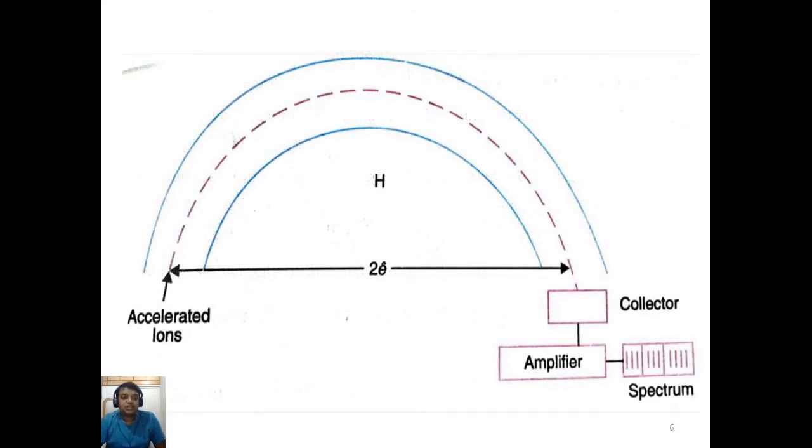This is the actual circular path of travel of the molecule from its release from the ionization chamber, entering into the electrostatic analyzer, subsequently entering the magnetic analyzer, and ending with a pass to the detector.